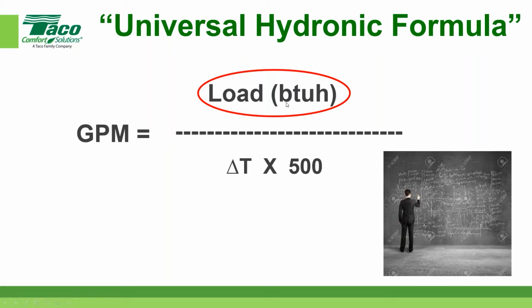Now, let's go back and remember what a British thermal unit was. It was the amount of energy it took to raise 1 pound of water 1 degree Fahrenheit. Nothing to do with gallons. So that's part of the conversion. We need to take pounds and turn them into gallons. And that's part one of the dual conversion. The other thing is a little easier. Notice it's British thermal units per hour, but we're solving for something that is based on minutes. So understand that difference as well. And there's your dual conversion.